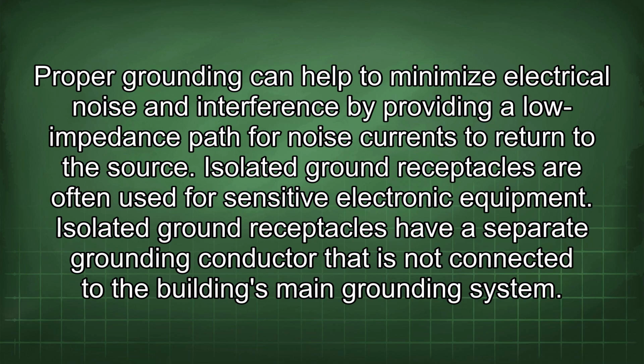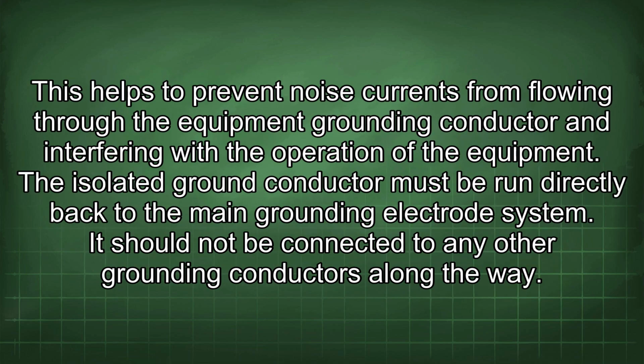Isolated ground receptacles are often used for sensitive electronic equipment. Isolated ground receptacles have a separate grounding conductor that is not connected to the building's main grounding system. This helps to prevent noise currents from flowing through the equipment grounding conductor and interfering with the operation of the equipment. The isolated ground conductor must be run directly back to the main grounding electrode system. It should not be connected to any other grounding conductors along the way.